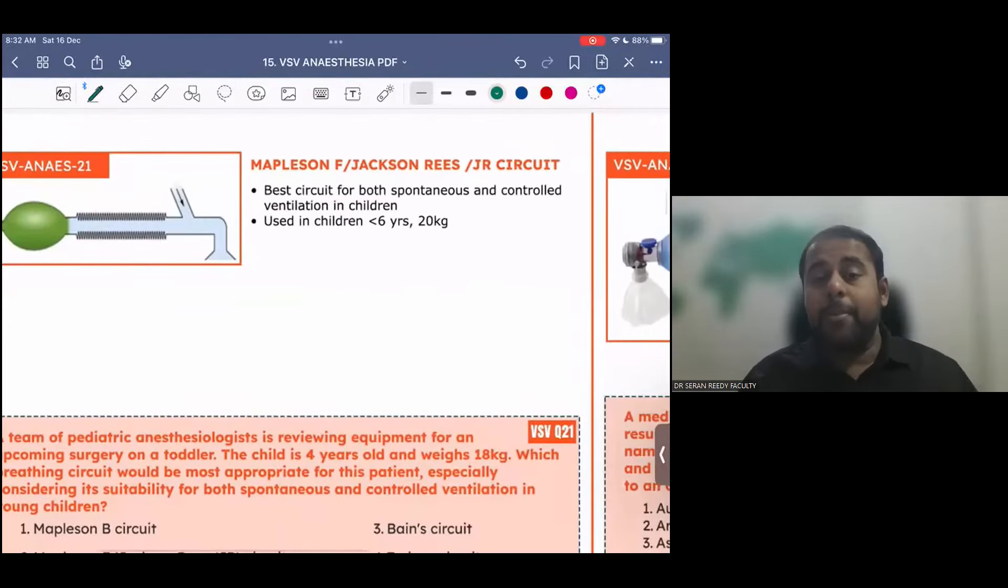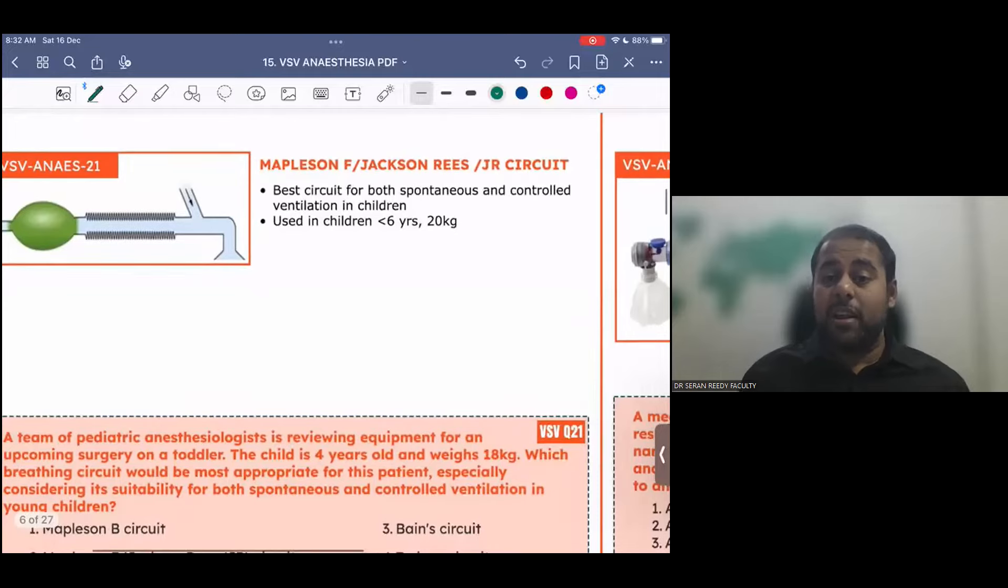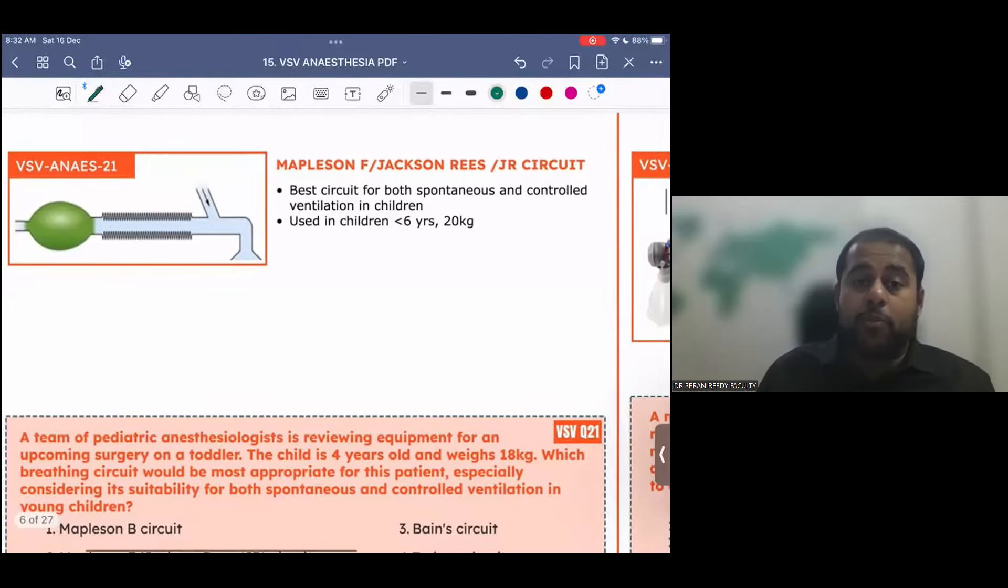This is called the Mapleson F circuit or Jackson Rees circuit or JR circuit. It is the best circuit for both spontaneous and controlled ventilation in children. How can you identify this? See, this doesn't have a closed APL valve. And this is the best circuit for both spontaneous and controlled ventilation in children. It is usually used in children less than 6 years and less than 20 kilos.